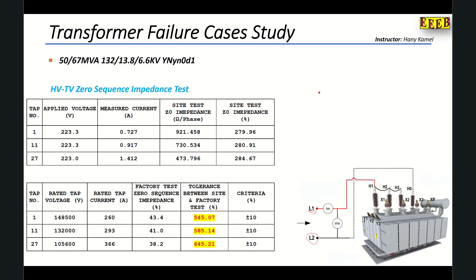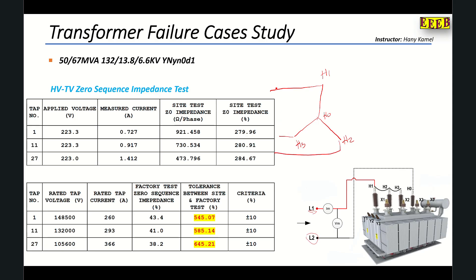We can see in the diagram: H1, H0, H2, H3 on the HV star side. The three HV phases are shorted and we apply the source between the shorted phases and H0. This represents the YN or 132 kV star side of the transformer.